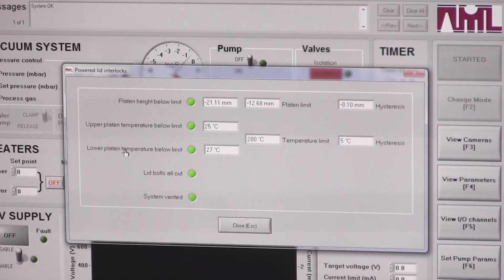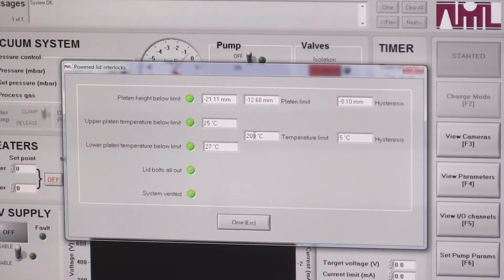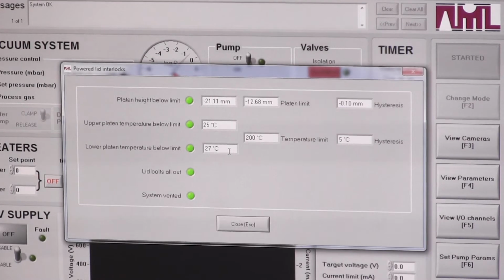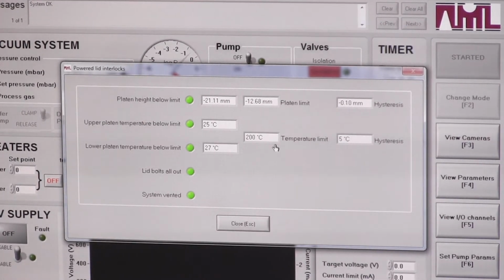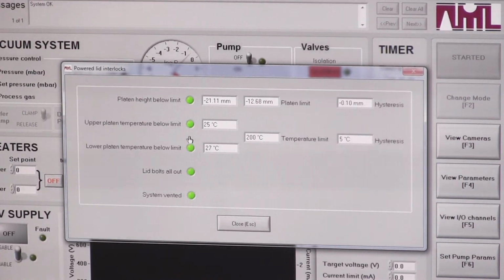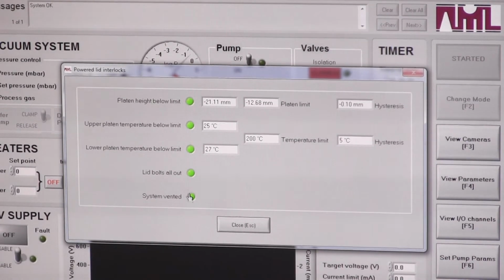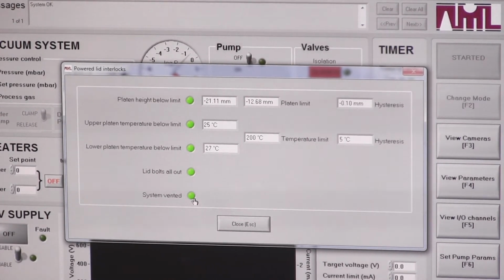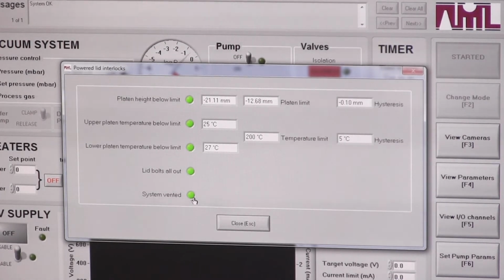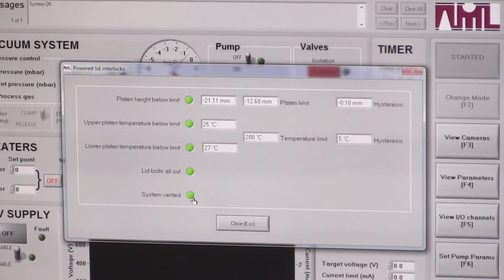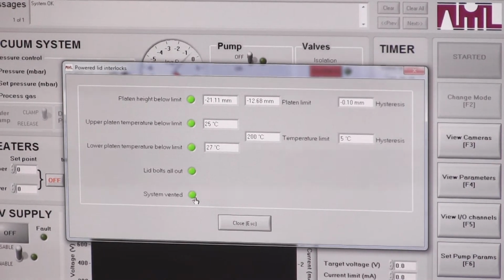Upper platen and lower platen below temperatures. The limit is set to 200 degrees. Currently they're both below that, so it's fine. If they were at 300, obviously these would be red until it had cooled down enough. Lid bolts out and the system vented. If the system is under vacuum, it will also not allow you to try and open the lid, because the lid's being sucked down by the vacuum. And again, that will grind the motor if you try to open it.